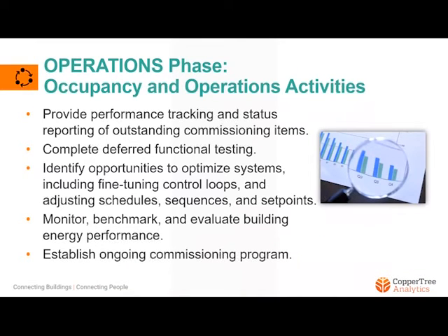Now, onto the operations phase of commissioning. Here are some of the activities during this phase. Provide performance tracking and status reporting of outstanding commissioning items. Complete deferred functional testing. Identify opportunities to optimize systems, including fine-tuning control loops and adjusting schedules, sequences, and set points. Monitor, benchmark, and evaluate building energy performance, and establish an ongoing commissioning program.